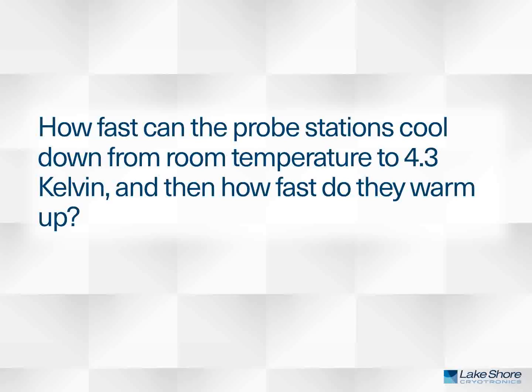Now, the larger systems are going to take a little bit longer. The systems with the integrated vertical field magnets, because of the heat capacity of the magnet, take a little bit longer to cool down and longer to warm back up again.